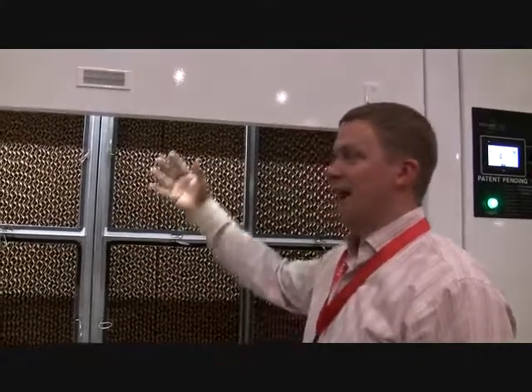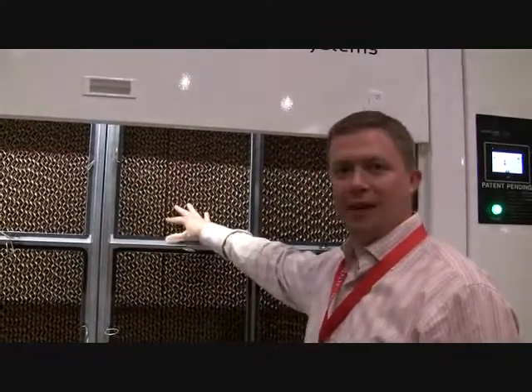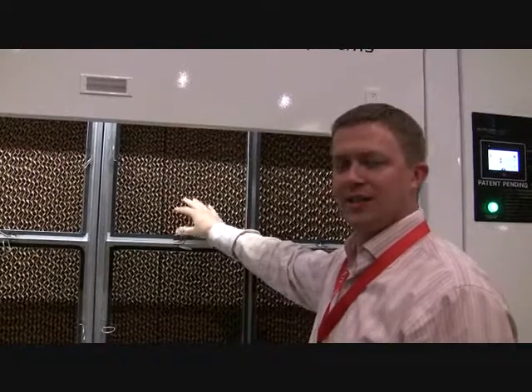It handles up to 3 inches external static. We use direct drive plenum fans. We introduce outside air through the evap. We typically get a 30 degree delta T through the evap and back out to the cold aisle. It's made for higher humidity climates.